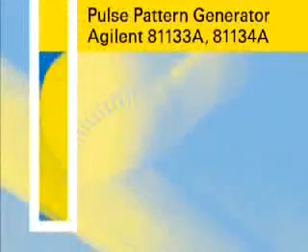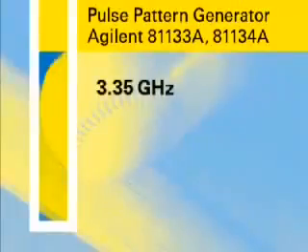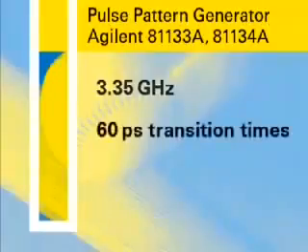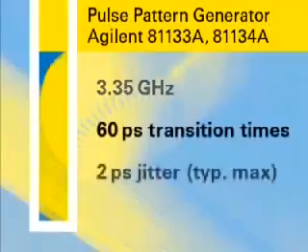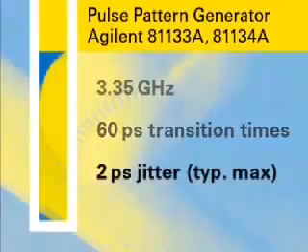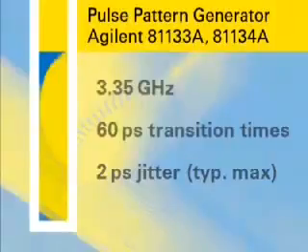This video will provide you with insight into the Agilent 81133A and 81134A 3.35 GHz high-speed pulse and pattern generator. The Agilent 81133A and 81134A are pulse and pattern generators with 3.35 GHz maximum frequency, fast 60 picoseconds transition times and typically less than 2 picoseconds of total jitter. The 81133A is a single channel generator while the 81134A is a dual channel configuration.